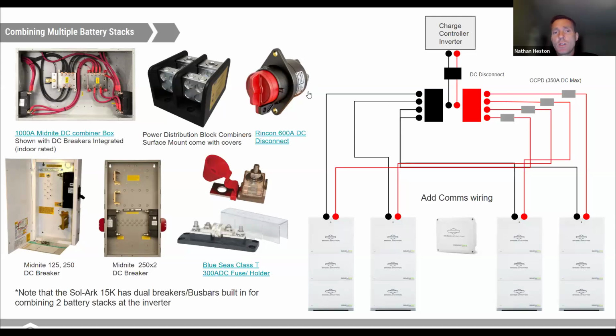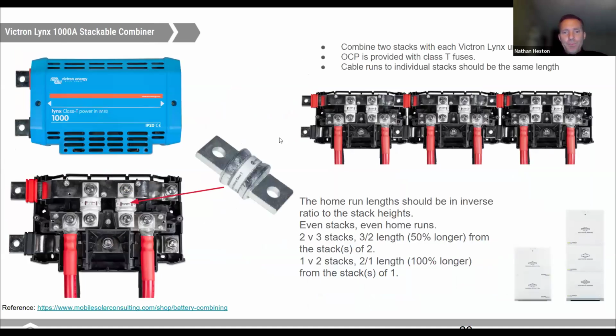These Rincon switches can be locked in the off position. They have the UL certification, and these go up to much higher voltages. I think they're rated at 600, even some of them are at 1000 amps. About $100, maybe a little more than that now. But these Rincon switches are a nice example, and there's a link there for those as well.